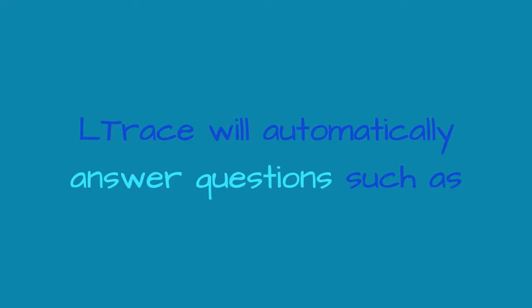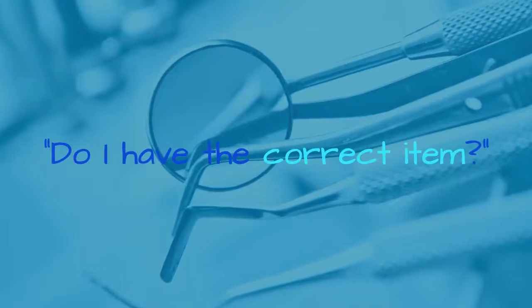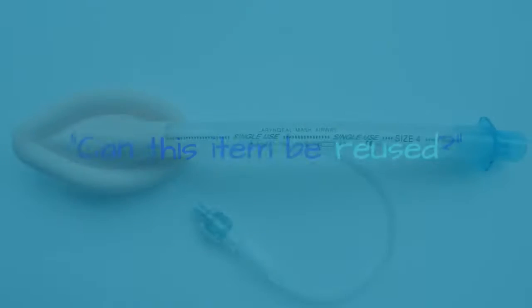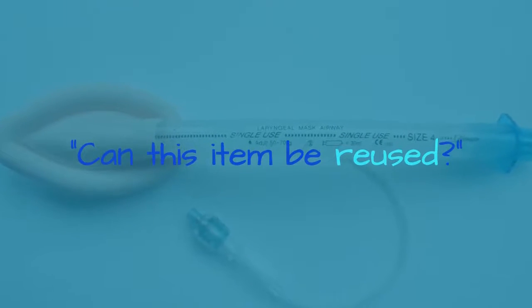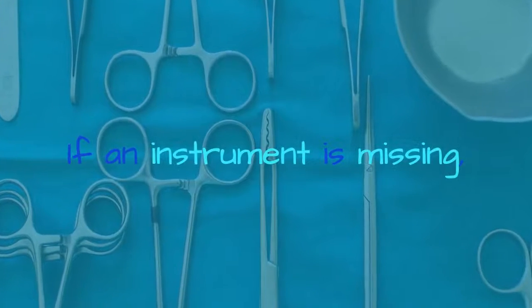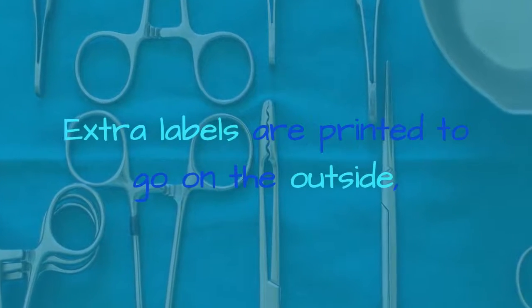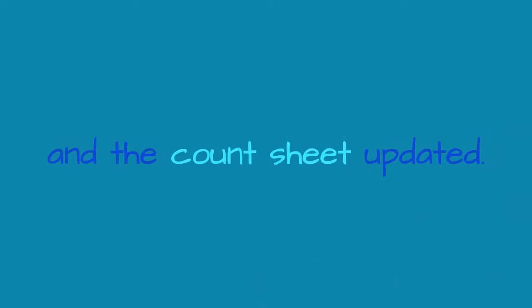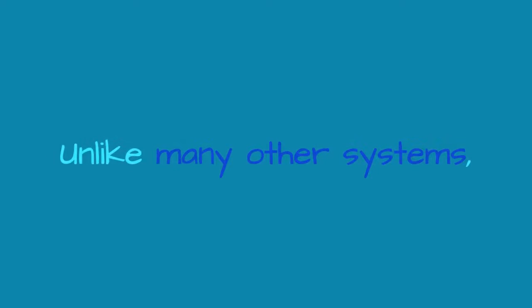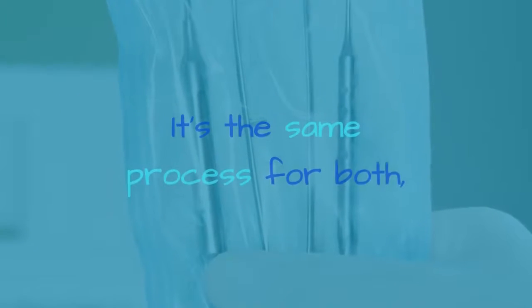It is all there in one location. L-Trace will automatically answer questions such as: how do I process this item, do I have the correct item, can this item be reused, and what do I need to be aware of? If an instrument is missing, this information can be recorded. Extra labels are printed to go on the outside and the count sheet is updated. Unlike many other systems, L-Trace does not distinguish between trays and steripeel items — it's the same process for both, keeping it simple.